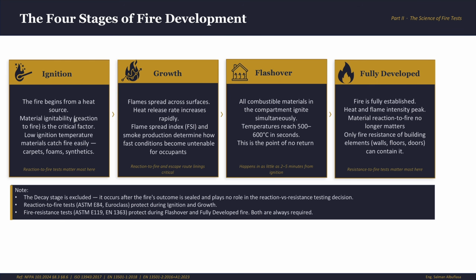So, starting out with the ignition phase, the fire begins from a heat source. A heat source meets a material. The material's ignitability determines whether it catches fire or not. Let's take an example: polyethylene and mineral wool. Polyethylene ignites at around 340 Celsius, but mineral wool does not ignite at any temperature encountered in a normal building fire. But this is where the reaction to fire matters most. The test answers: how does this material behave when fire first meets it?